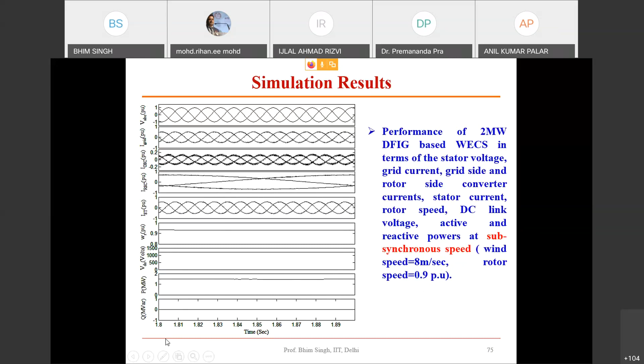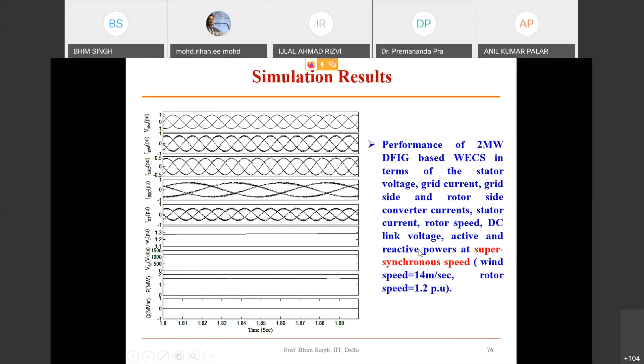So this is below synchronous speed. I told you 0.9 per unit with this wind speed, and you can see the low frequency. In this case, you will find the rotor power is negative below synchronous speed, and you can see the power generation on the stator side or grid side, and the reactive power generation is 0 on the stator side. Or this is corresponding to the super synchronous speed region, 1.2 where 14 meters per second, and again you have reactive power 0, but you have active power generation. All those parameters are there, and your speed is obviously above synchronous speed, like 1.25 per unit.